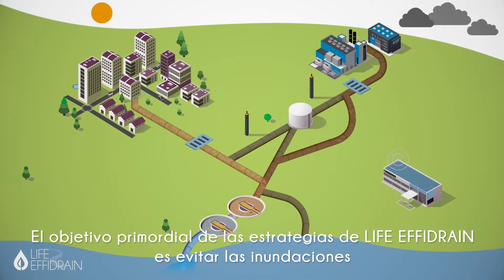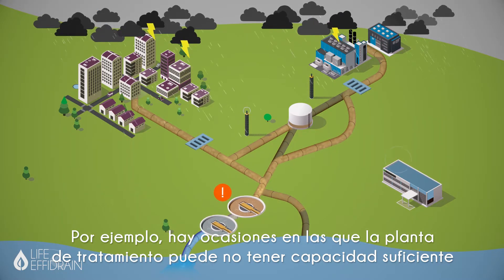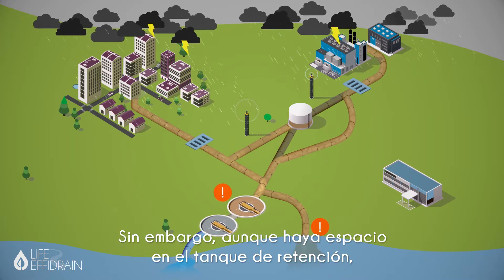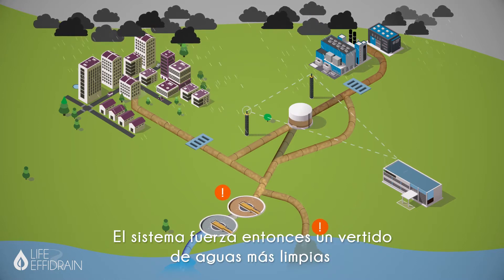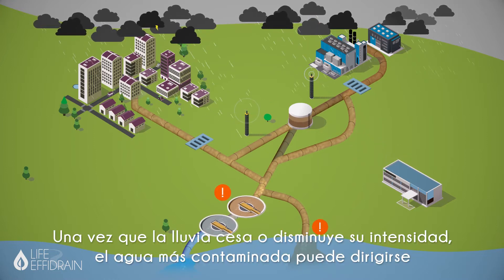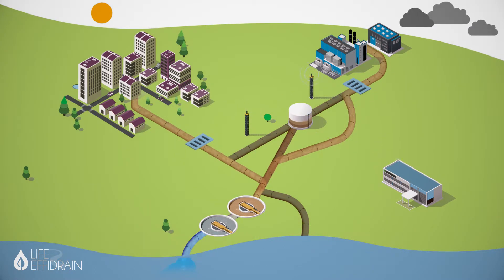The LIFE EFFIDRAIN strategies always aim to avoid flooding and reduce the level of pollution released into the environment. For example, there are times that the treatment plant may not have enough capacity to treat all the wastewater. However, although there is space inside the retention tank, a decision not to store it might be taken in order to have free volume to store more polluted water that has been predicted to come in the following time instance. The system then forces a sewer overflow of cleaner water to prevent the more polluted water from overflowing. Once the rain has decreased its intensity or stopped, the most polluted water can go to the treatment plant.